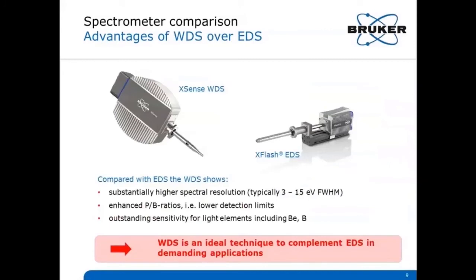As WDS and EDS actually measure the same physical property, it is important to realize that there are some main differences between the two techniques. First, a substantially higher spectral resolution of WDS compared with EDS — typical values are in the 3 to 15 electron volt range, meaning 10 to 20 times better than EDS. Second, enhanced peak-to-background ratios, which translates into lower limits of detection, up to about 100 ppm.